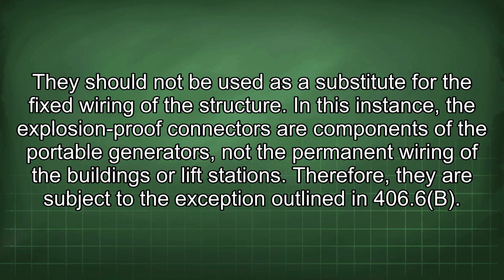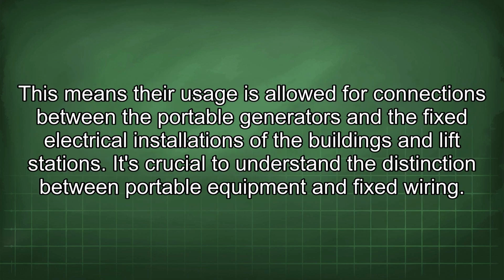In this instance, the explosion-proof connectors are components of the portable generators, not the permanent wiring of the buildings or lift stations. Therefore, they are subject to the exception outlined in 406.6b. This means their usage is allowed for connections between the portable generators and the fixed electrical installations of the buildings and lift stations. It's crucial to understand the distinction between portable equipment and fixed wiring.